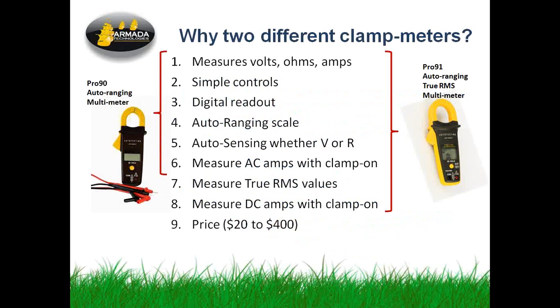Why do we have two different clamp meters? The Pro90 is the fundamental simple meter that we sell. It does all the things that you need to do for most multimeters. It has volts, ohms, and ampere measurement capability. It has simple control. The ease of usability and simplicity are a main issue here, especially for people that are not electrical people. Auto ranging scale for the same reason. Auto sensing measures AC amps through the clamp. Great thing for lighting systems as long as they're incandescent type systems. You can measure the power.